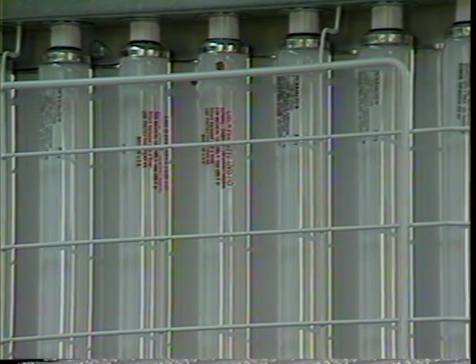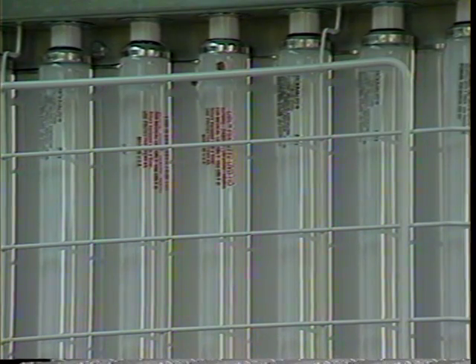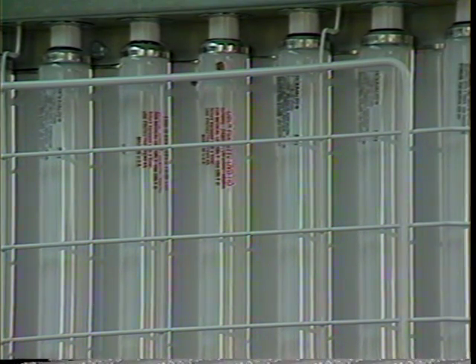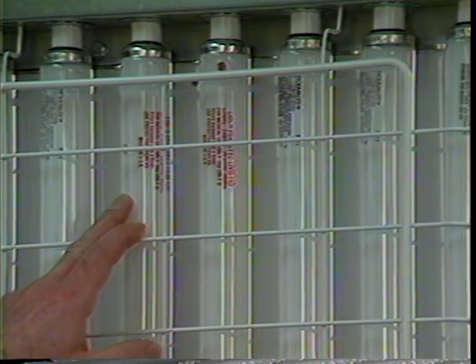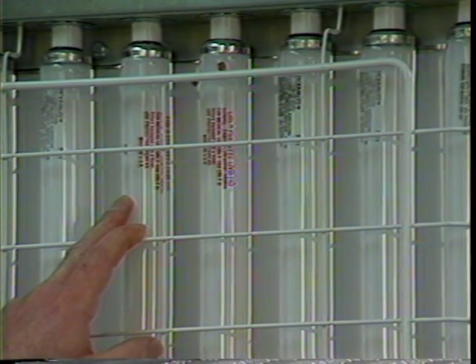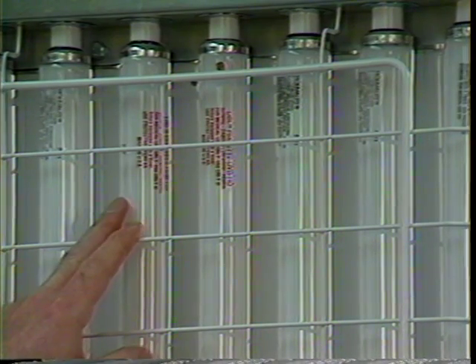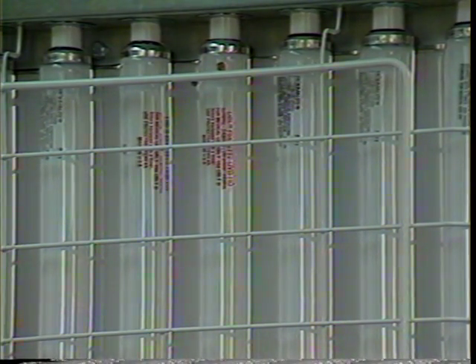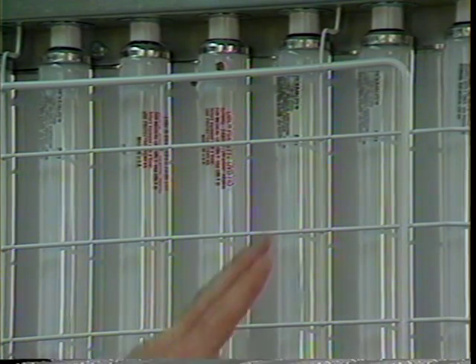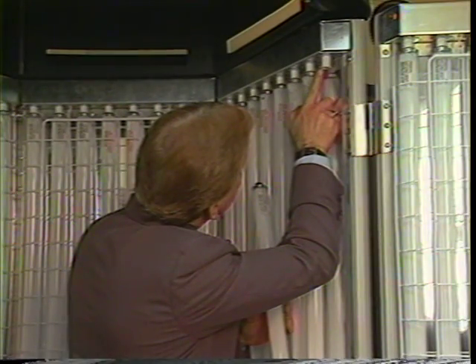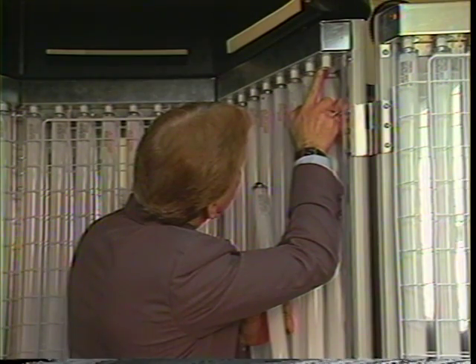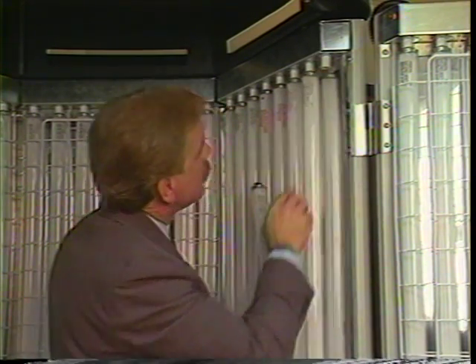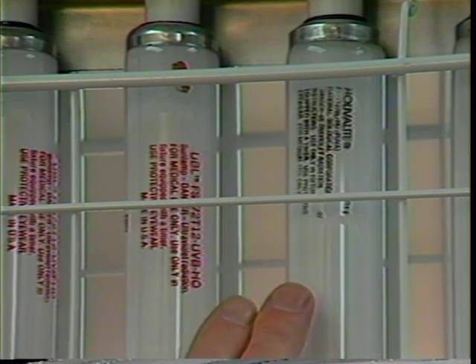It is important to be able to easily distinguish between the UVA and the UVB lamps inside the unit. The UVB lamps are the center two lamps in each section and are clearly marked with red monogram labeling. The UVA lamps are the three lamps on either side of the UVB lamps, and they are clearly marked with black monogram labeling. The UVB lamp has a specifically designed base which makes it impossible to interchange it with a UVA lamp. This is a vital safety feature found in no other phototherapy system except the HOUVA II from National Biological Corporation and represents one of the most important features of our device.